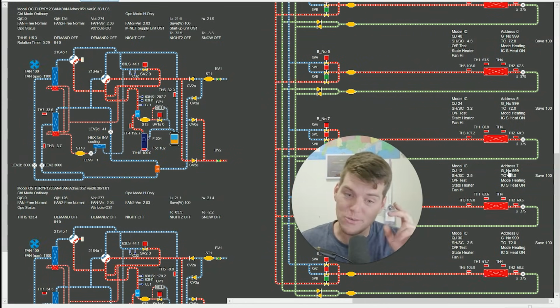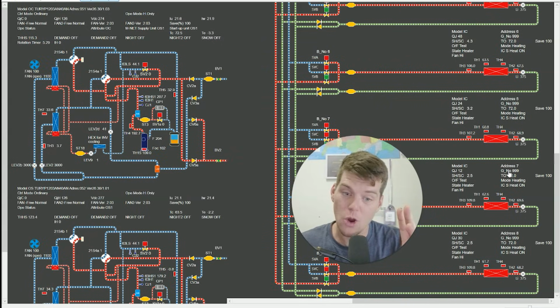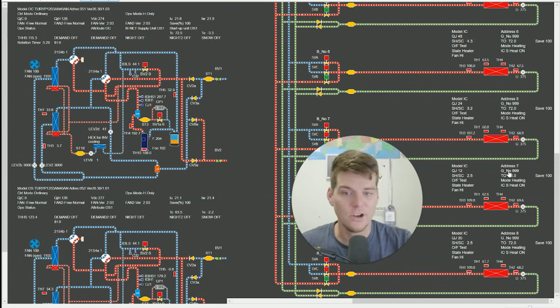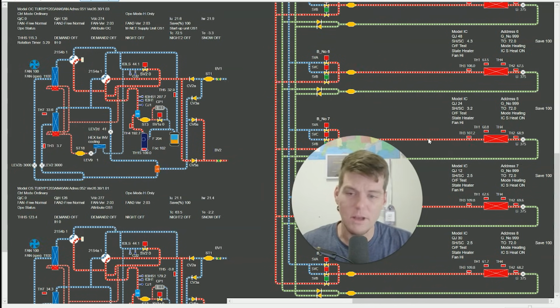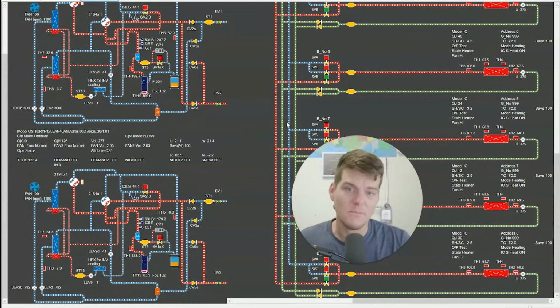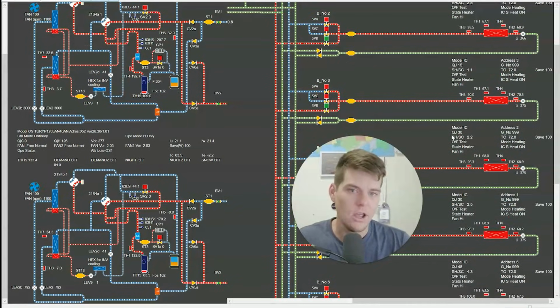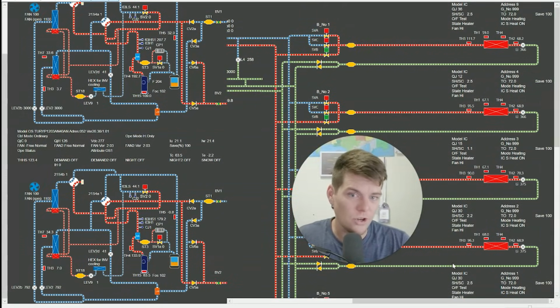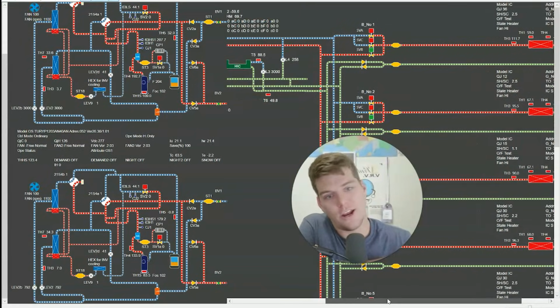So high discharge superheat, high suction superheat, low subcooling, almost got me there saying high, means that it looks like it's undercharged, but that only pertains to the master module. What's going on in the submodule? Well, the submodule doesn't reflect the same thing. If it did, then maybe we'd start to hang our hat on charge discrepancies or even low charge. But let's keep this train a rolling here.